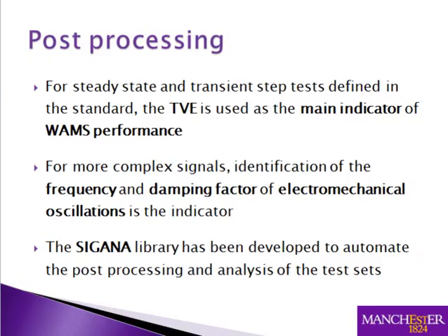Now the most interesting part is obviously post-processing. So there were like two indicators. The main indicator for the tests in the standard was the TVE, and for more complex signals like the ones simulated in DIgSILENT, we identified the frequency and damping factor of electromechanical oscillations, and we compared it with DIgSILENT's embedded model analysis. That was the main indicator. So we even developed the SIGANA library, which automated the post-processing and analysis of the test set.